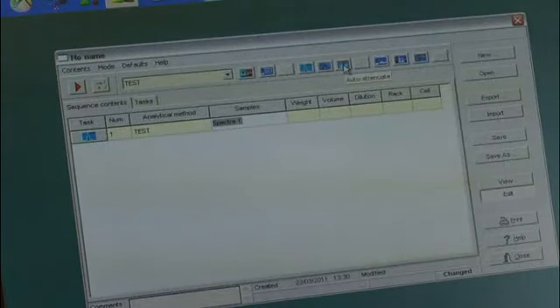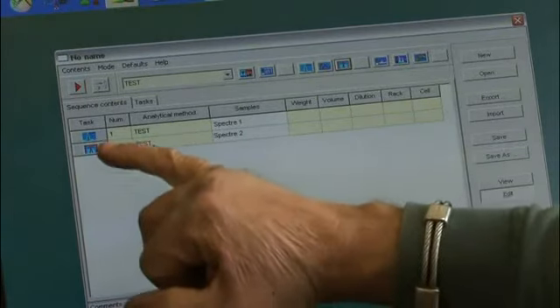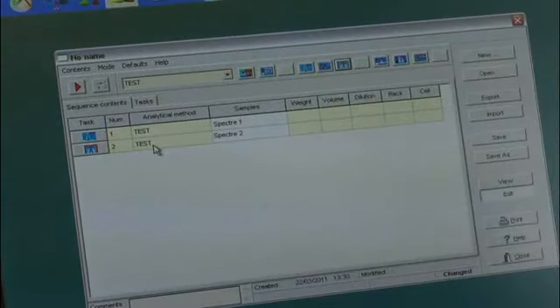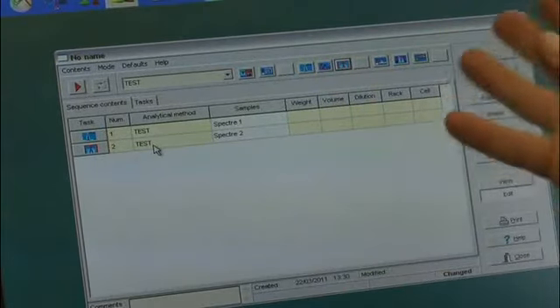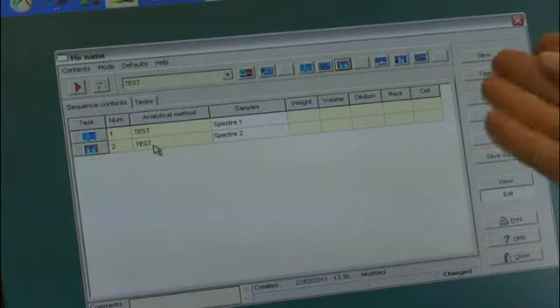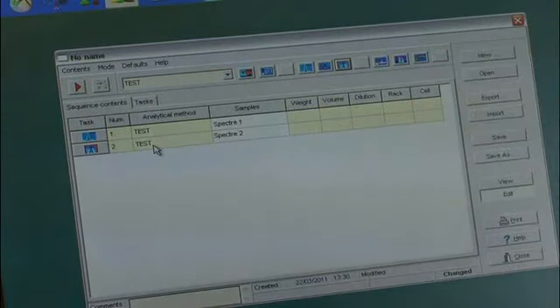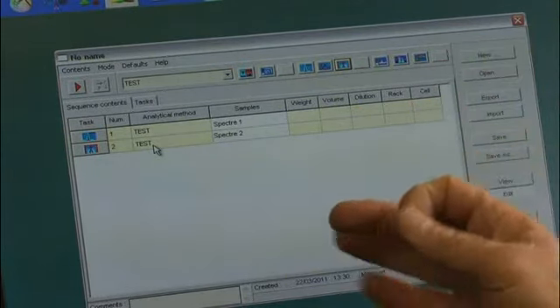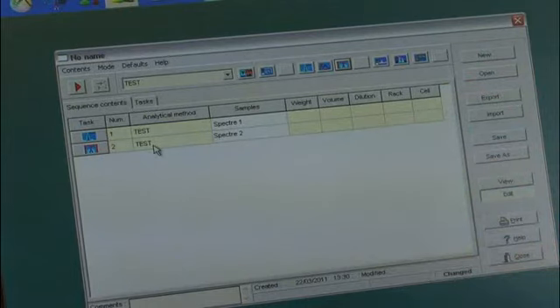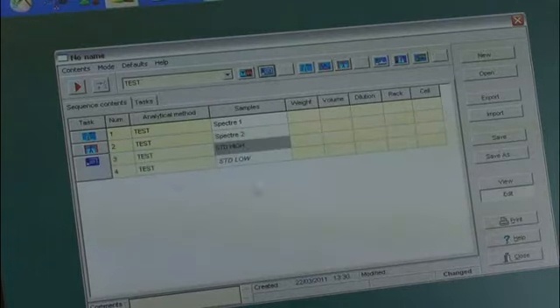Then I'm going to do an auto attenuate. The auto attenuate will then go to the top of where it found the peak and start adjusting the voltage and gain for the best setting that it thinks it should use every time it goes to that wavelength. And that's always done on your high standard. If you have 5 standards, you do it on the highest one of those 5. And then we're going to do a calibration.